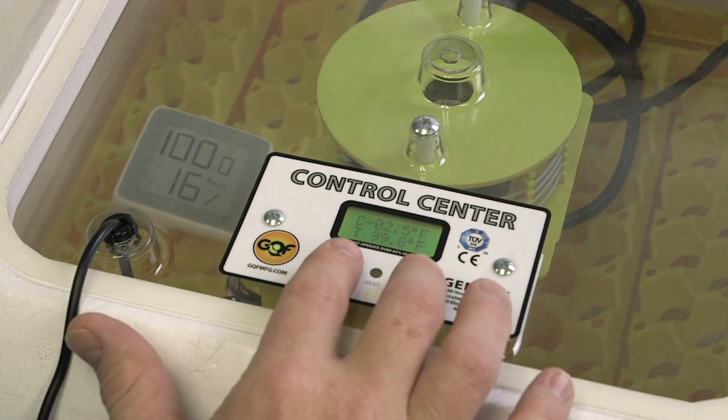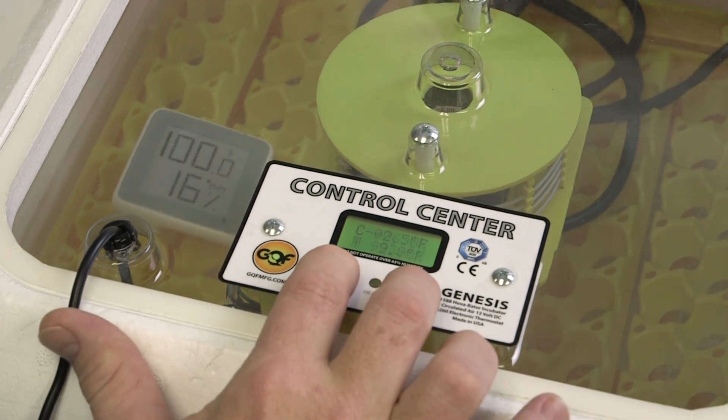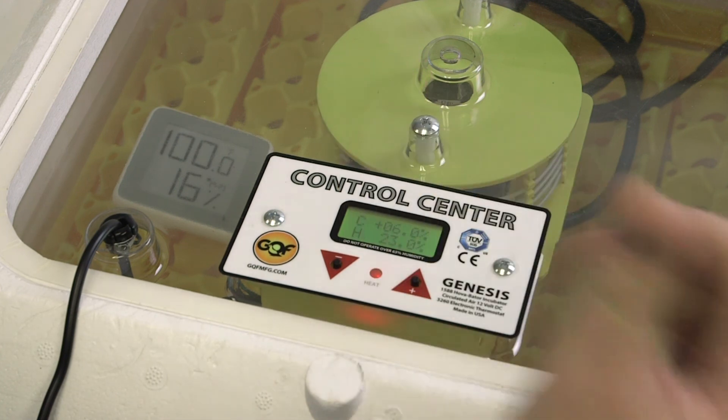Here, in order to advance to the next screen, hold both buttons for a few seconds. When you release it, you can actually calibrate your humidity if you feel the need to do so.